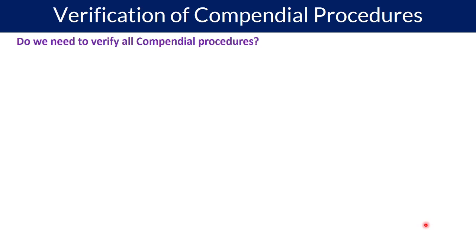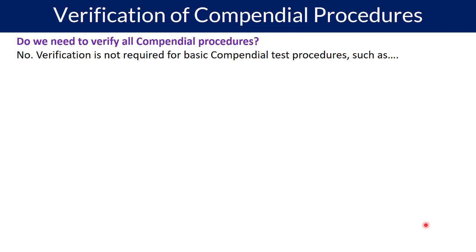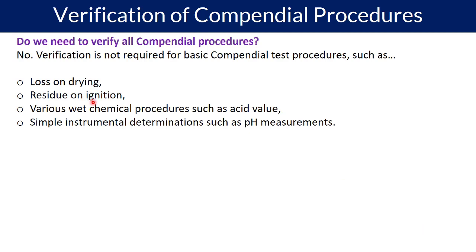Do we need to verify all compendial procedures? You are not only using identification, impurity, or assay procedures — there are several others such as pH measurement and loss on drying. According to USP General Chapter 1226, verification is not required for basic compendial test procedures. Examples include: loss on drying, residue on ignition, various wet chemical procedures such as acid value, and simple instrumental determinations such as pH meters.